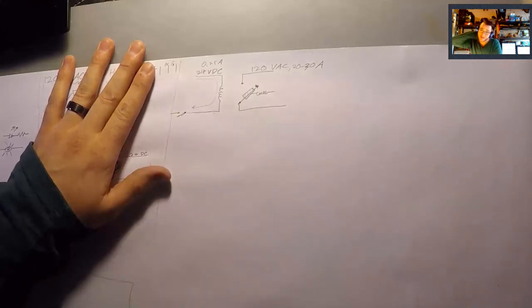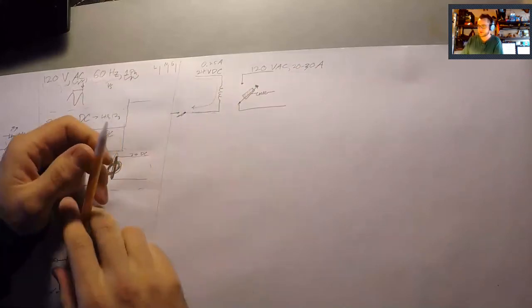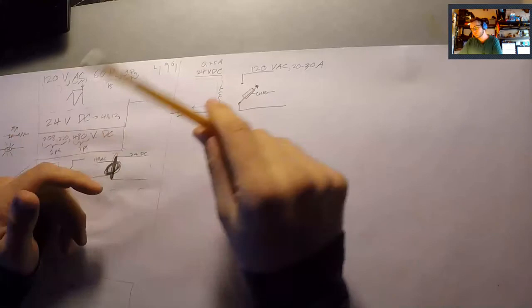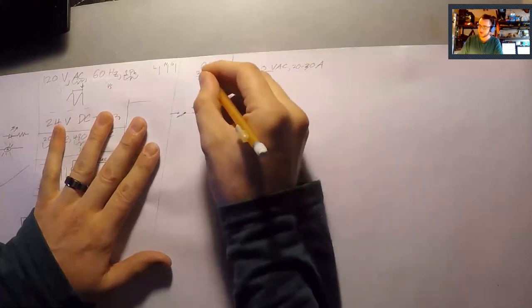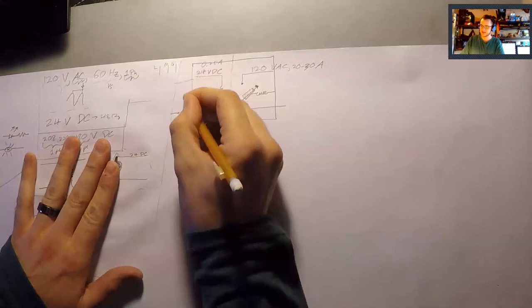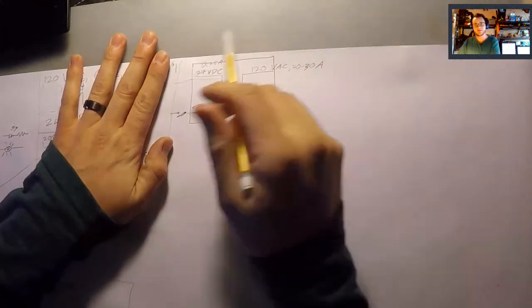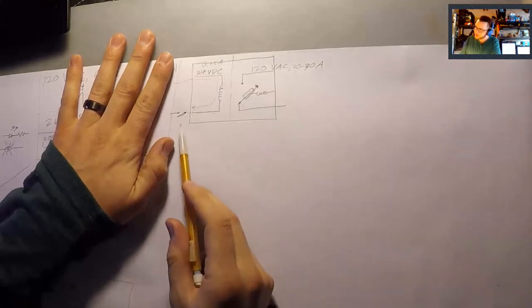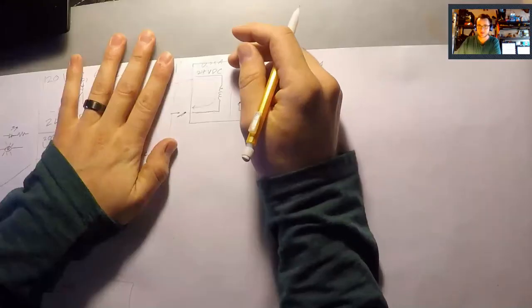At 24 volts and a quarter of an amp, Bob is going to go home just fine — he's not even really going to feel it. But on the high-voltage side of that circuit, if Bob were to slip and stick his finger in there, Bob's probably not going home that day. All the relay circuitry is in a little plastic box — you run wires to it on the control side and keep the switch far away from all the dangerous moving parts and high voltage, protecting your operator with physical barriers.